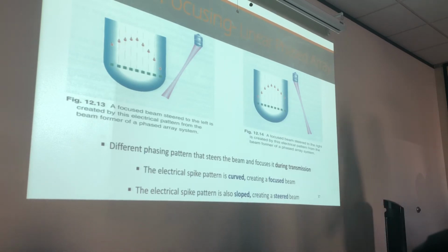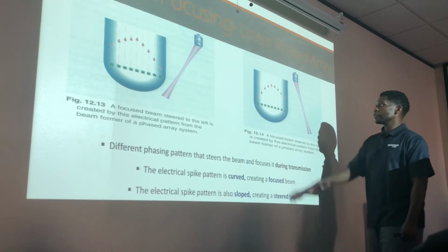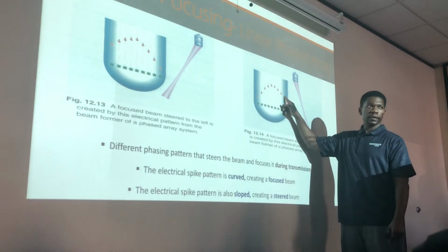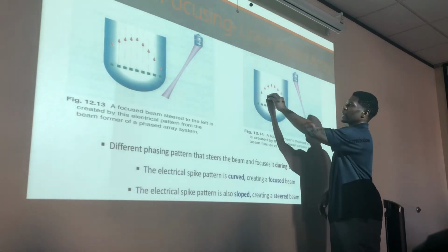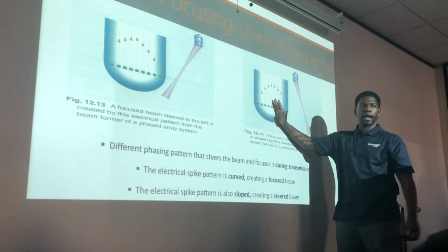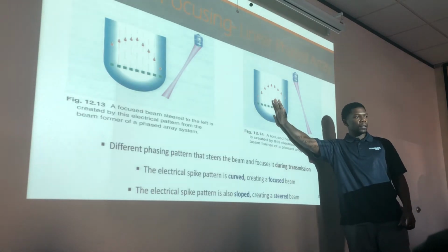Okay? Same thing applies. Different phasing pattern that steers the beam, focuses it during transmission. Again, we're only talking about transmission right now. Transmit focusing. Okay? The electrical spike pattern is curved, creating a focused beam. The electrical spike pattern is also sloped, creating a steered beam. That same kind of rule can still apply if you want to know which way it's being steered, right? So with this one, if I draw a straight line from here to here, that's going to give me a line like that. I draw a line perpendicular to that, and I know which way this beam is being steered. Okay? You can use that same rule, just use the outside elements in this case.